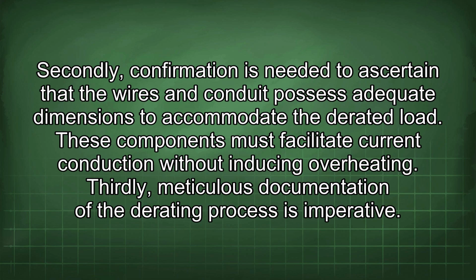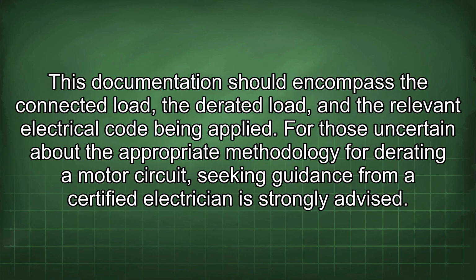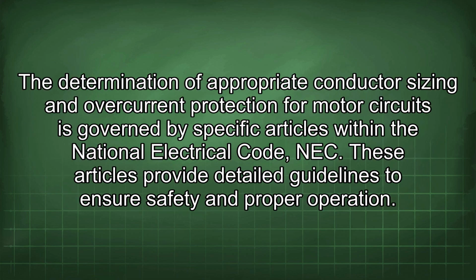Thirdly, meticulous documentation of the derating process is imperative. This documentation should encompass the connected load, the derated load, and the relevant electrical code being applied. For those uncertain about the appropriate methodology for derating a motor circuit, seeking guidance from a certified electrician is strongly advised. The determination of appropriate conductor sizing and overcurrent protection for motor circuits is governed by specific articles within the National Electrical Code (NEC). These articles provide detailed guidelines to ensure safety and proper operation.